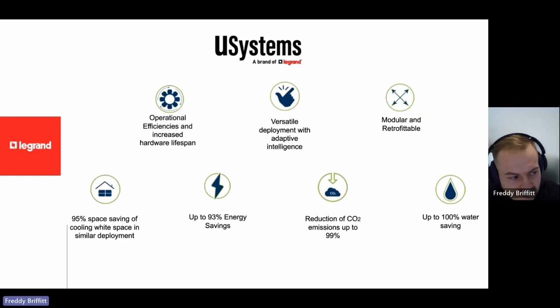So that's how we do what we do, but what benefits does that bring? So there's operational efficiency. Because we're so close to the back of the active equipment, we can utilize really, really warm water. So we can use typically a 20-30 flow and return, which will enable us to benefit from free cooling. And it also means that our fans are working not as hard as the fans on equipment that's not as close to the source of the heat. So our power draw is really, really low, and we have a fantastic EER.